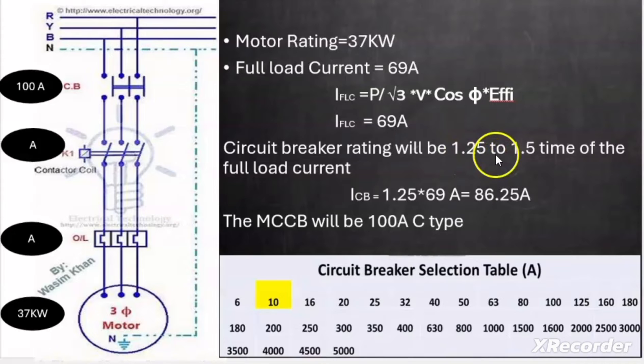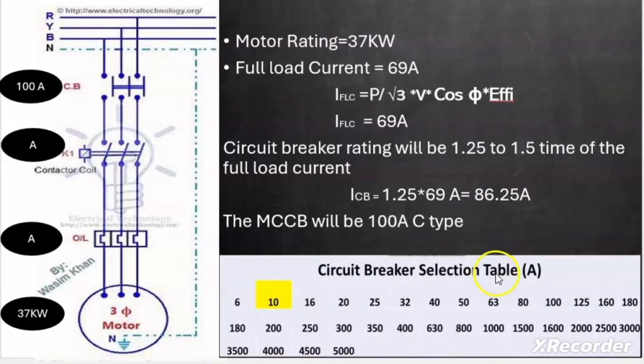You can also calculate the full load current using a formula. The circuit breaker rating will always be 1.25 to 1.5 times the full load current. Here I took the safety factor as 1.25, so the circuit breaker rating is 1.25 × 69A = 86.25A. Since circuit breakers come in standard sizes, we select the next higher standard size, which from the selection chart is 100 ampere.